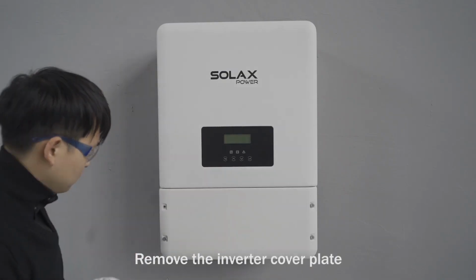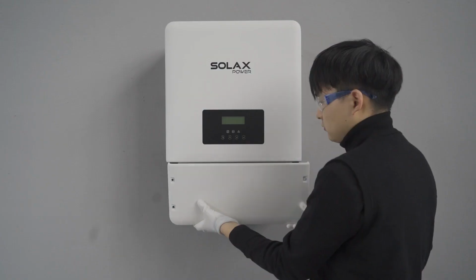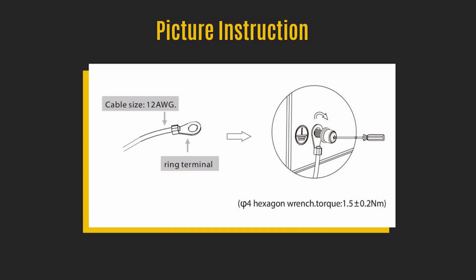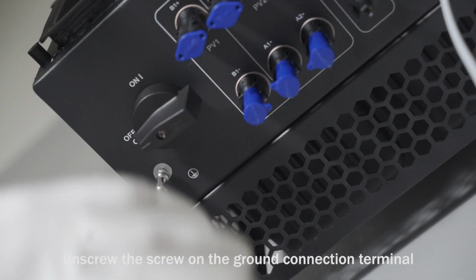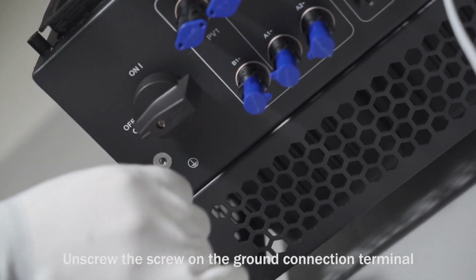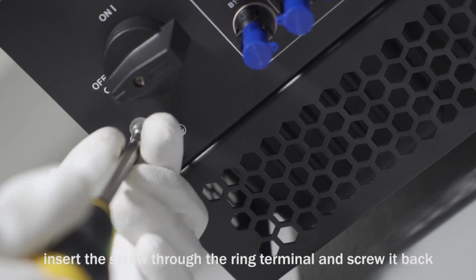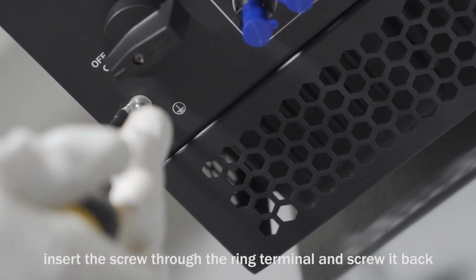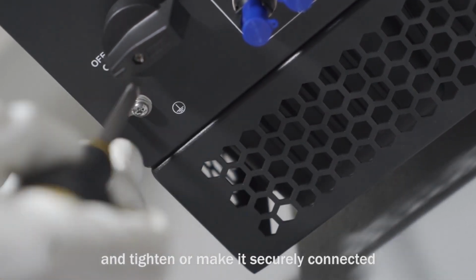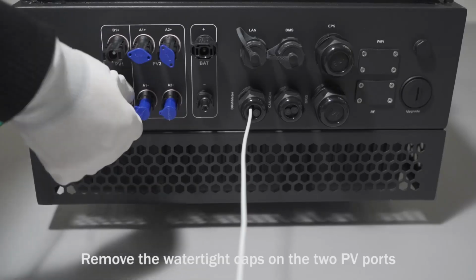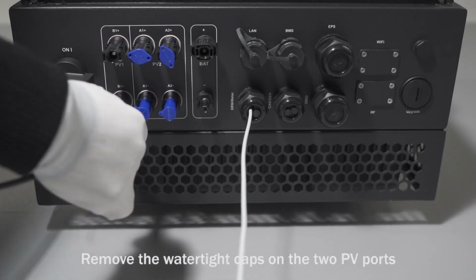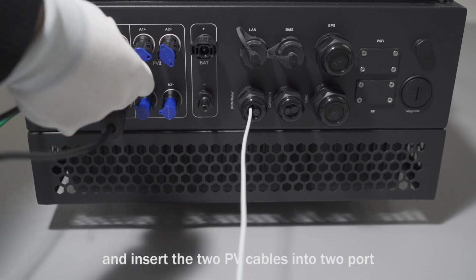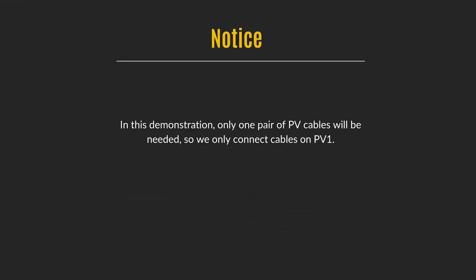Remove the inverter cover plate. Unscrew the screw on the ground connection terminal. Insert the screw through the ring terminal and screw it back, and tighten it so it is securely connected. Remove the watertight caps on the two PV ports and insert the two PV cables into the two ports.